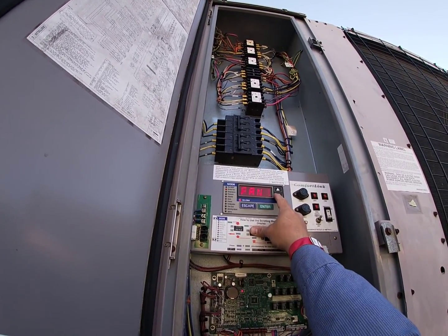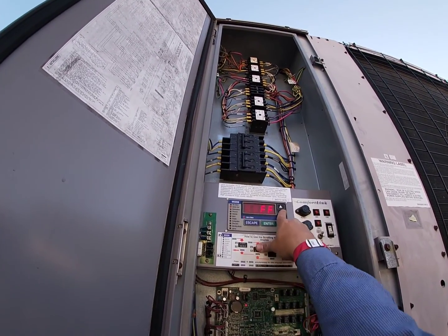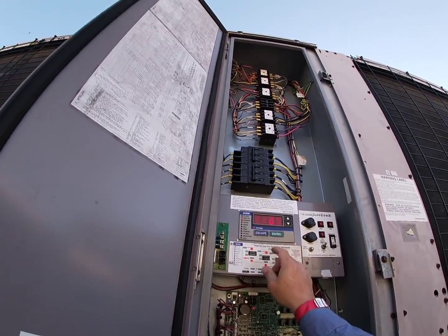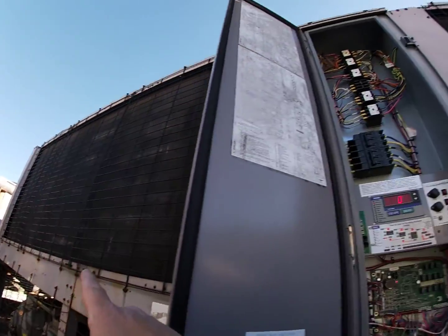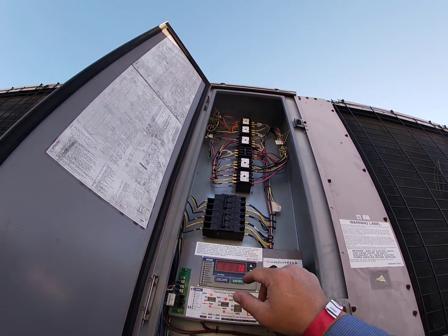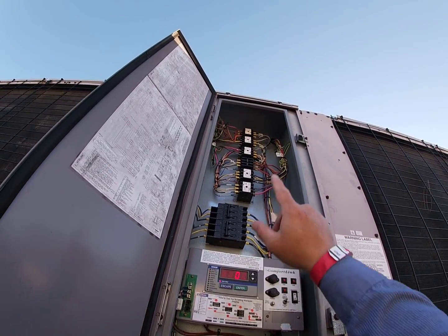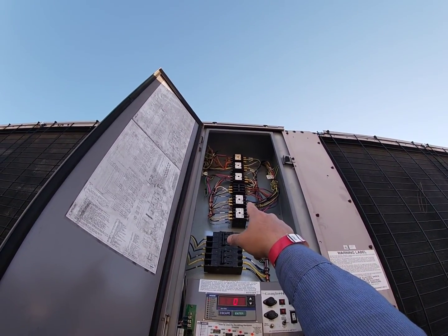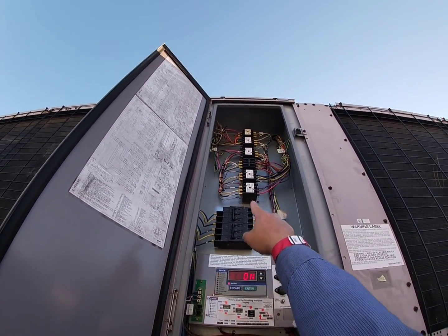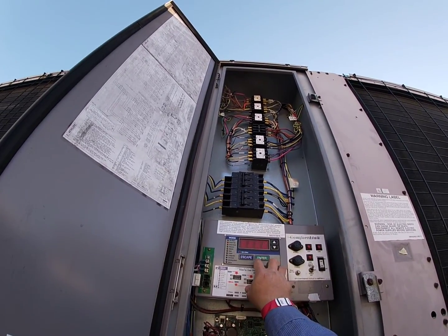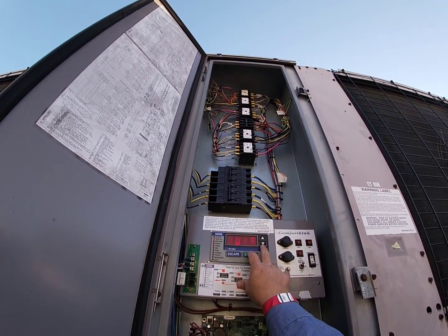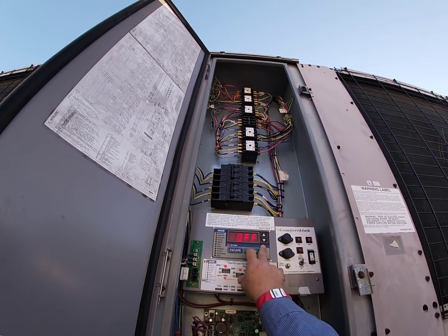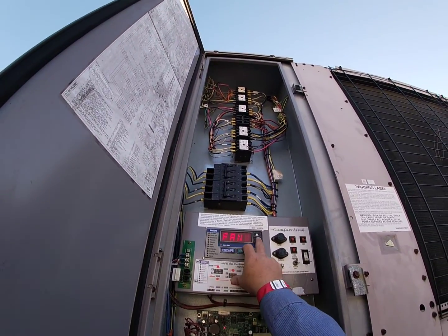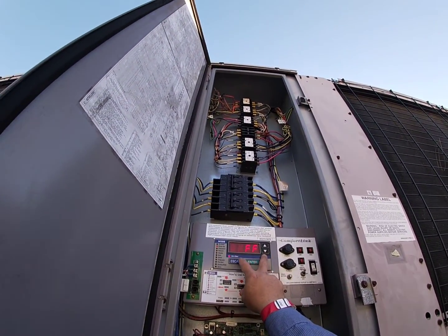Look for condenser fan motor 1, we're going to turn that on. Contactor pulled in, I can hear that condenser fan motor running. Which contactor pulled in up there? Oh, that one there, so it's just a single, the third one. That's actually on this breaker here, just a single one that pulled in, so we're good there. We're going to turn that off and go to fan 2.